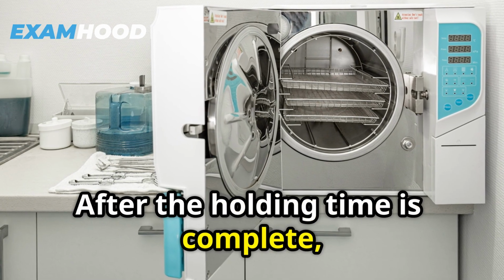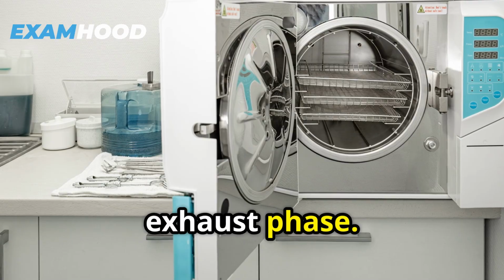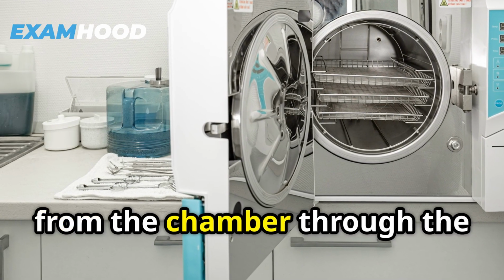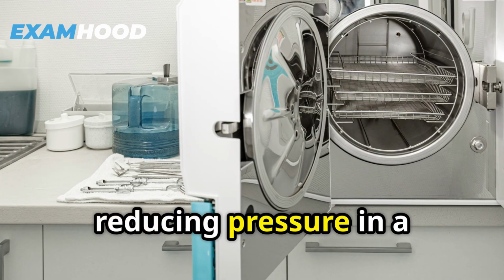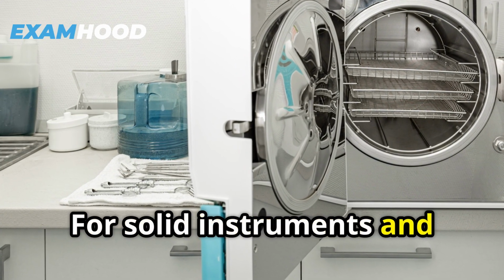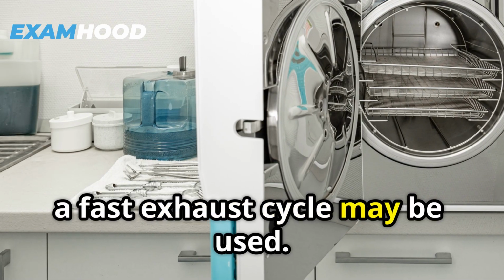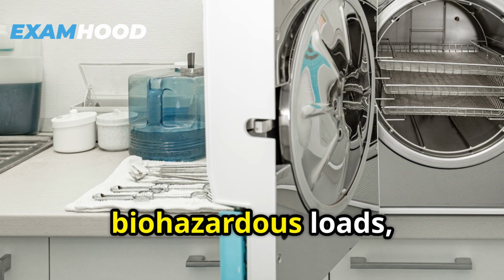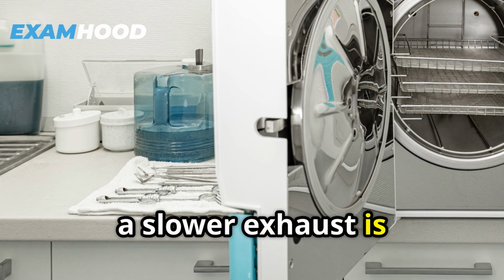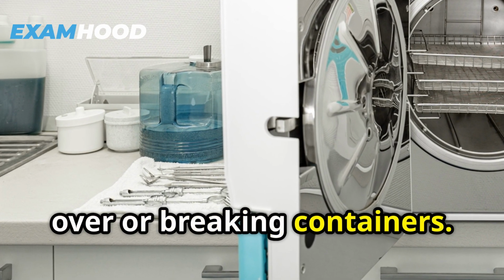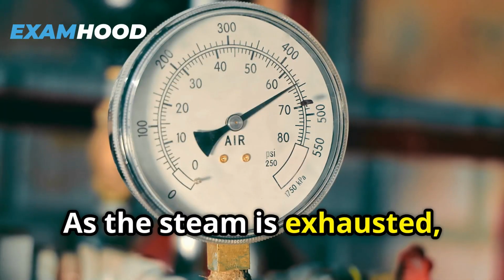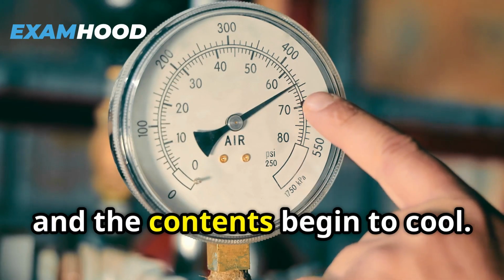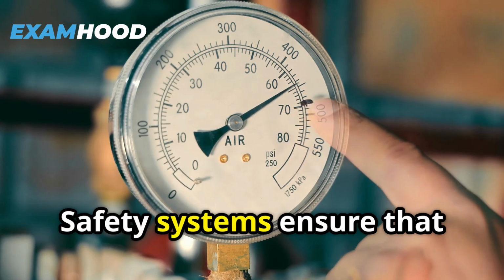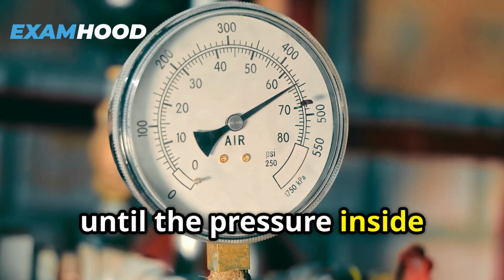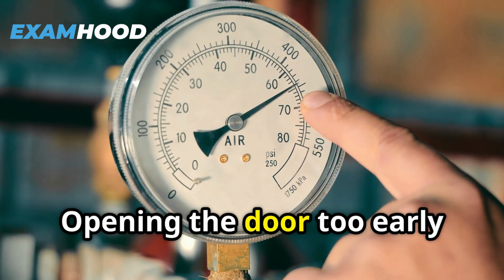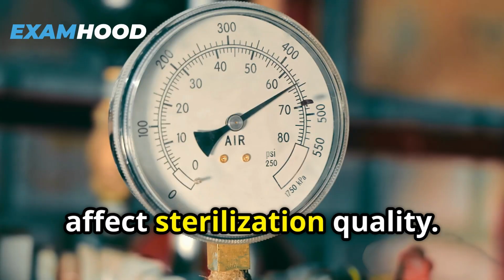After the holding time is complete, the autoclave begins the exhaust phase. In this step, steam is slowly released from the chamber through the exhaust outlet, reducing pressure in a controlled manner. For solid instruments and dry materials, a fast exhaust cycle may be used. For liquids and some biohazardous loads, a slower exhaust is required to prevent boiling over or breaking containers. As the steam is exhausted, pressure drops back toward normal, and the contents begin to cool. Safety systems ensure that the door cannot be opened until the pressure inside the chamber is safe. Opening the door too early can be dangerous and also affect sterilization quality.